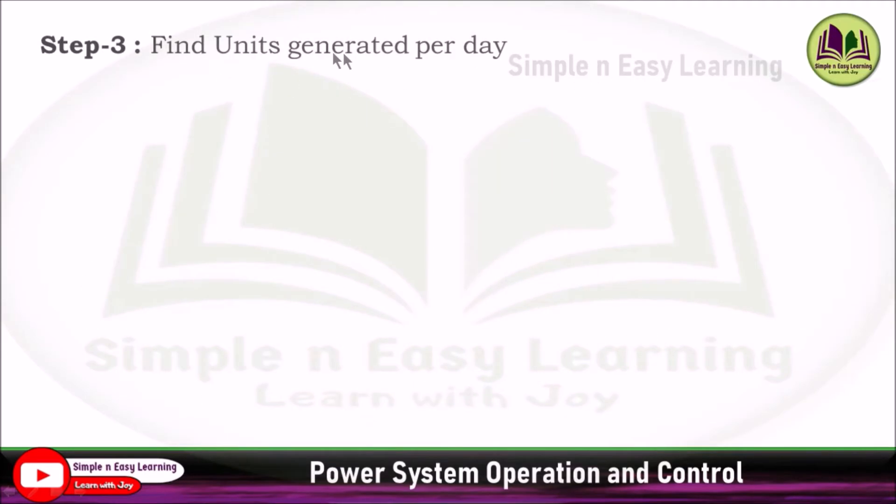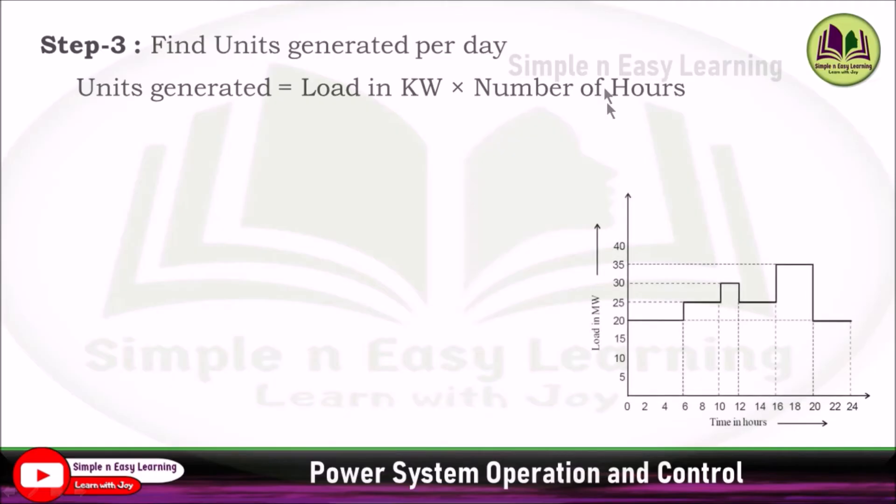Step 3: find units generated per day. Units generated equals load in kilowatt times number of hours. Consider this load curve. Take the load and the number of hours. First one, 0 to 6, that is 6 hours, 20 megawatt of load is consumed, so 6 into 20. Next one, 25 megawatt for 4 hours 6 to 10, and 30 megawatt for 2 hours, so 30 into 2. Then 25 megawatt again for 4 hours, 25 into 4. Then 35 megawatt into 4 hours 16 to 20. And finally 20 megawatt for 4 hours, 20 into 4.